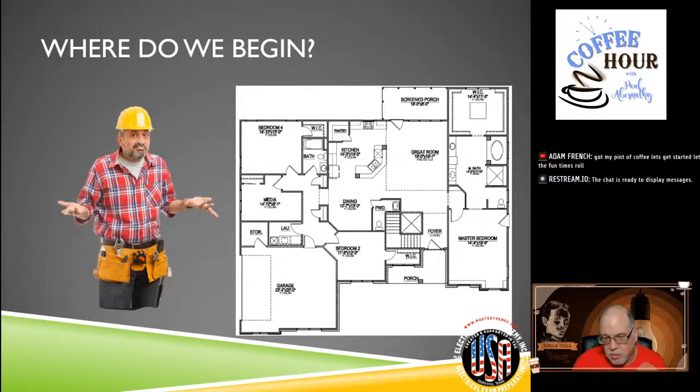6 and 12s, countertops, you know, 2 feet from the ends, 2 feet from sinks, 2 feet from breaks in the counter. I'm going to do 4 feet spacing between them. I'm going to do all those type of things, right? The normal. But if I'm doing it with a customer, I want to ask them, do you have anything special that you need me to have a receptacle outlet at or whatnot like that? And that's what I'll really mark on the plans. Whereas if I'm not going to put everything on the drawing, then I'm going to at least mark with them things that they request. And at the end, in that nice big space at the bottom or somewhere on the plans, I get the customer to sign it. This is what we agreed to. But again, if it's just a spec, we're just going to lay it out as normal.